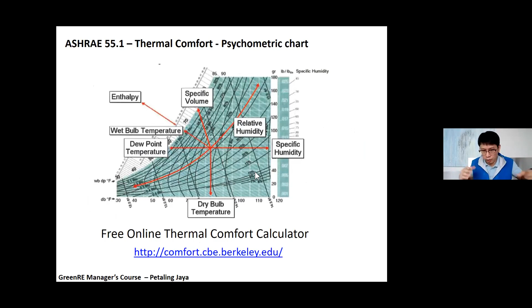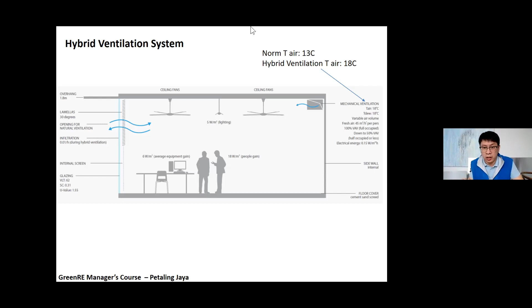Just a quick example: for this project in Singapore, the normal supply air temperature is usually about 13 degrees Celsius to get that 24-25 degree room temperature. But in this case, because we're running hybrid, we have ceiling fans plus mechanical ventilation giving fresh air, so we pump air at 18 degrees Celsius, with ceiling fans as well.